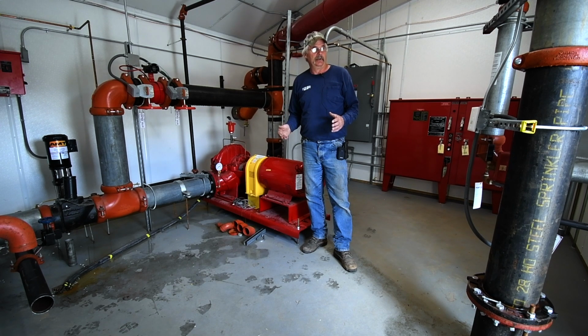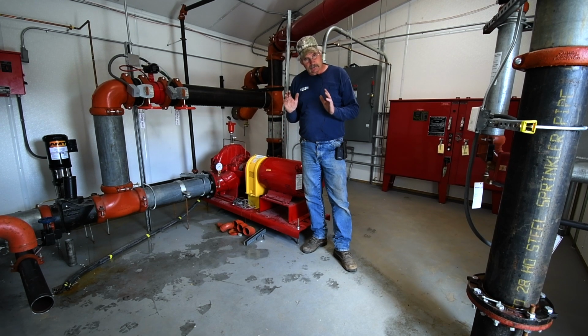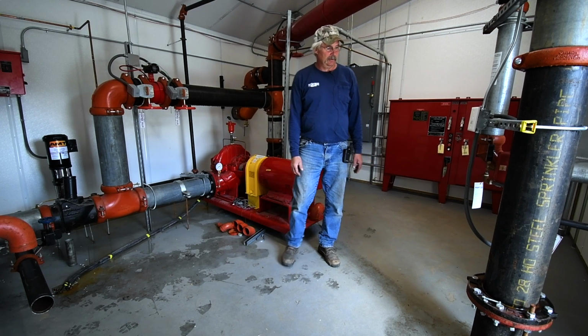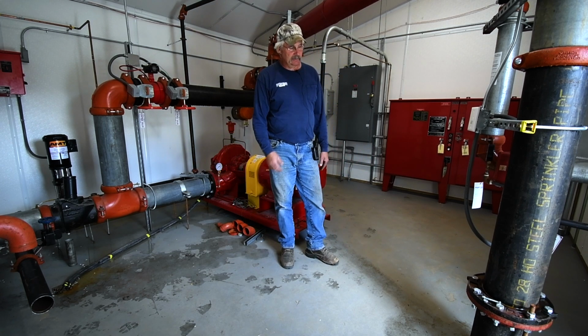All you have to do during a fire is get out of the building. It's fully automatic. It's not made to have you come in the building and turn a valve off, turn a valve on. Just get outside the building. After the fire and it's put out, that's when you can go through the steps. Shut control valve A, open main drain B, open inspector's test C, call the number, and we're on our way to help you.